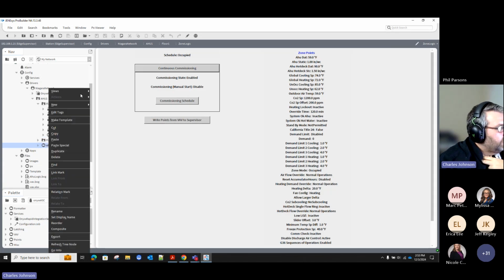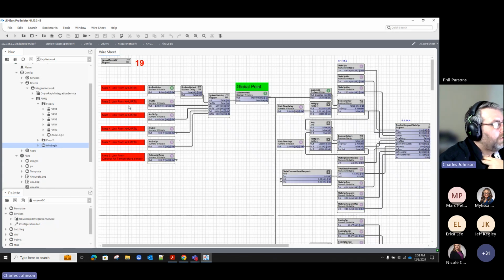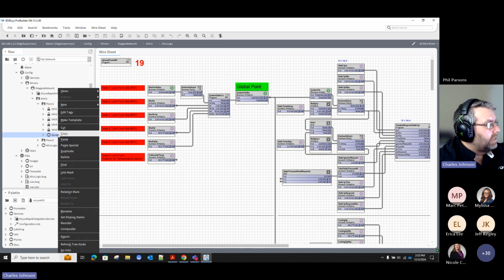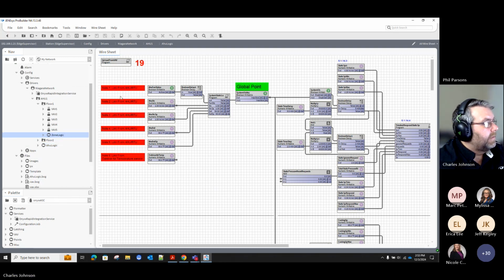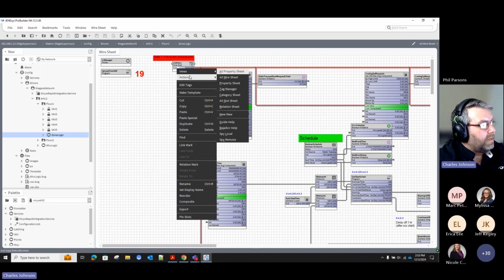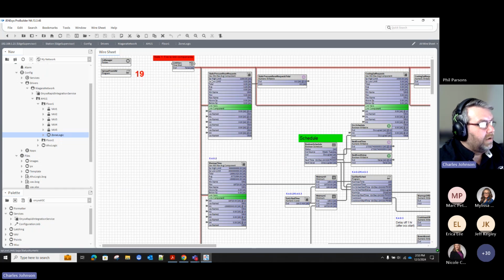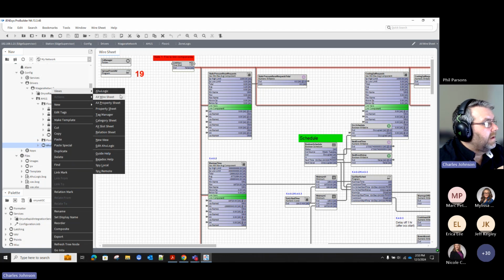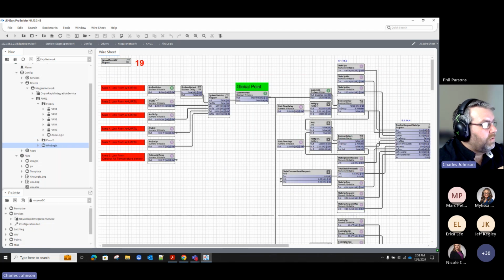With the AHU logic, we've already created a bunch of logic for you. In the zone logic folder, all you do is hit link VAVs, and it will link all the VAVs—static pressure requests, cooling requests, heating requests, warm up and cool down—and your AHU logic will link from a specific air handler.